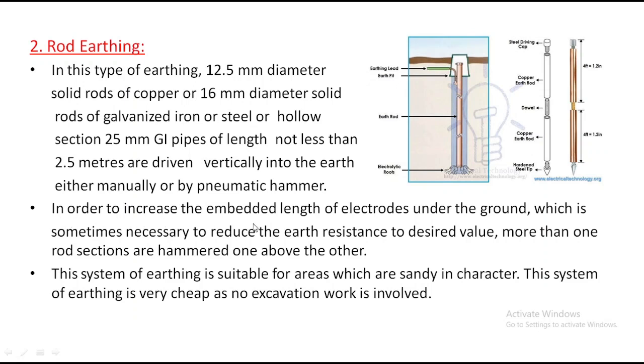In order to increase the embedded length of the electrodes under the ground, which is sometimes necessary to reduce the earth resistance to the desired value, we can increase this length. Sometimes, to increase the current rating, we have to reduce the earth resistance. More than one rod section can be hammered one above the other. Look at here, we can use 2 rods here. We can increase the rod sections.